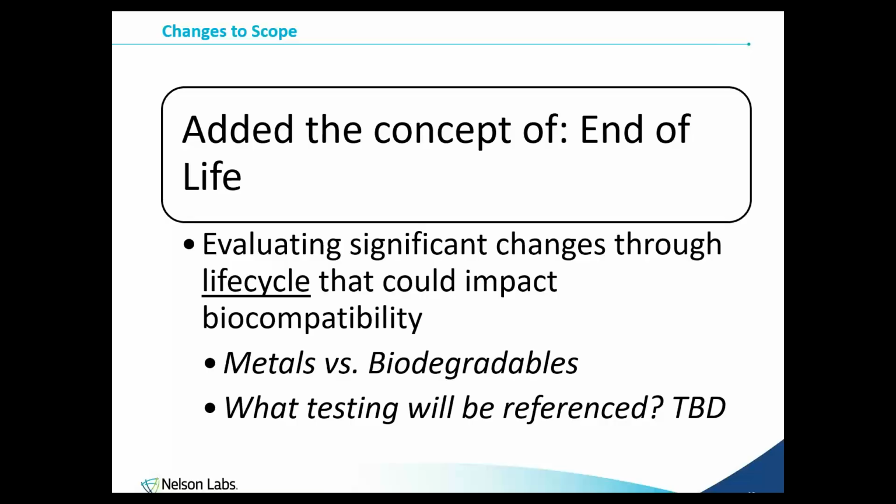And the concept here is most people do biocompatibility at time 0, which honestly is the right thing to do, because you have most of your volatile and maybe even semi-volatile compounds at time 0 that interact with the body. But especially polymers and other types of materials like that can change over time. So you have stabilizers, and other additives to polymers that are meant to help with different types of chemical degradations and things like that.